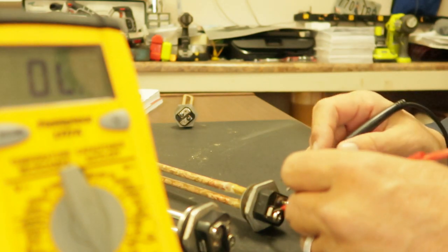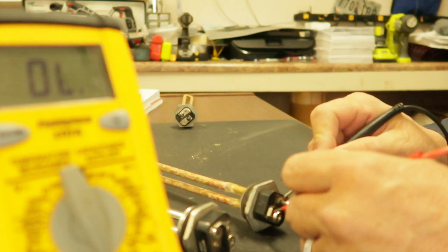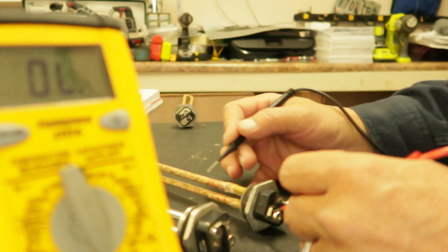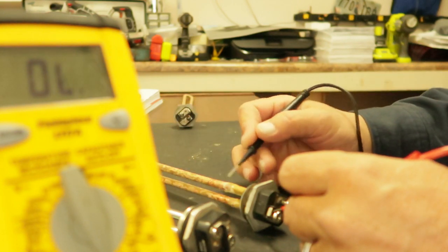First thing I'm going to do is check for resistance and see what that number gives me. It gives me OL. So chances are this element is bad. The element that goes inside of the rod is burnt off inside of there somewhere.